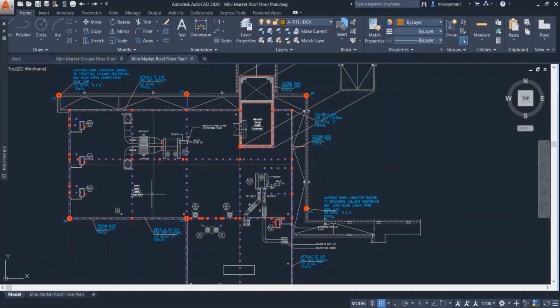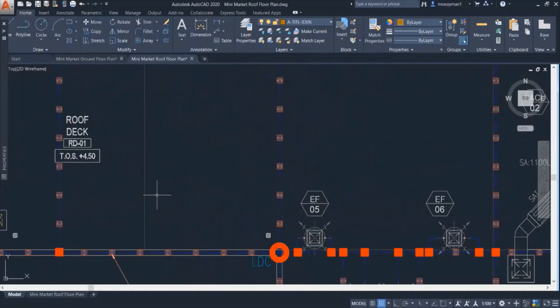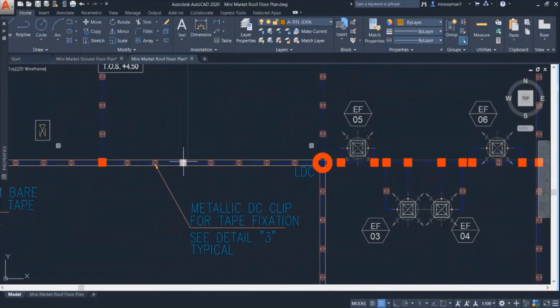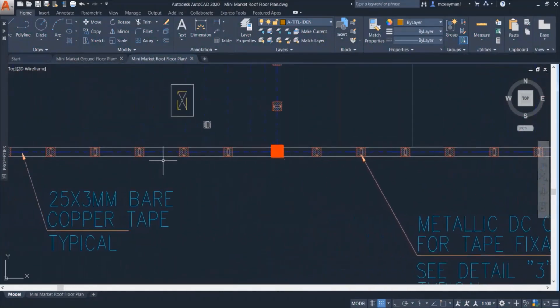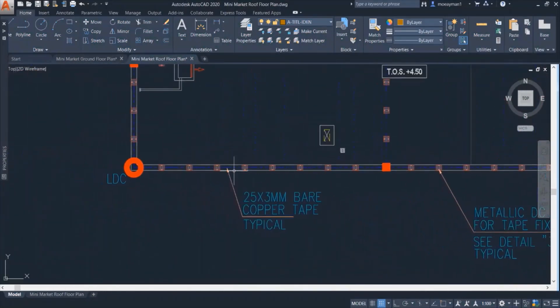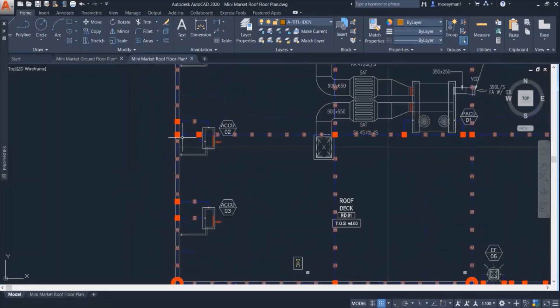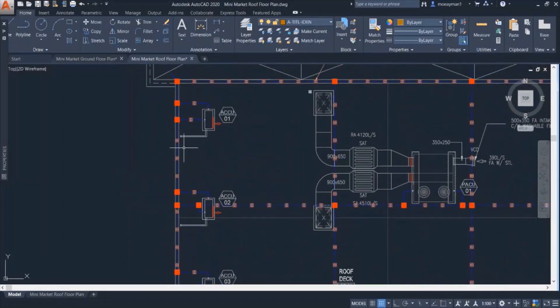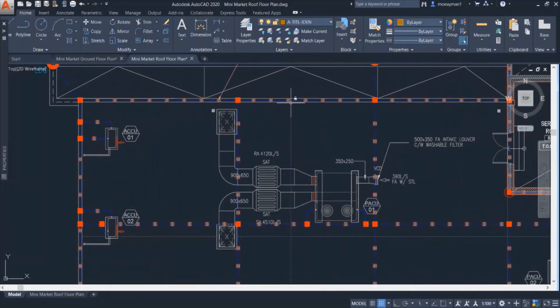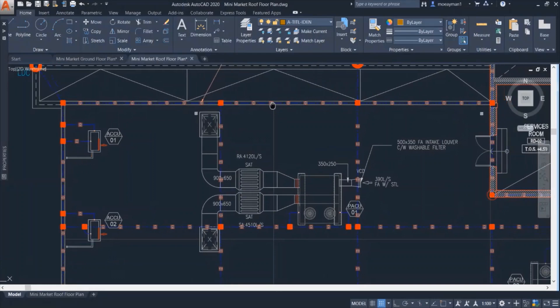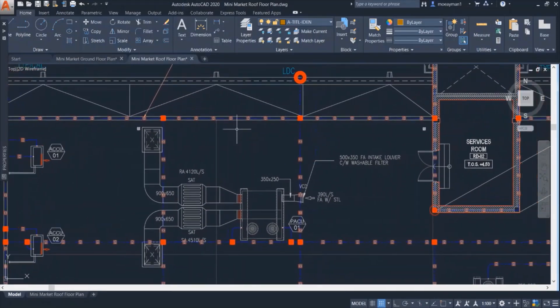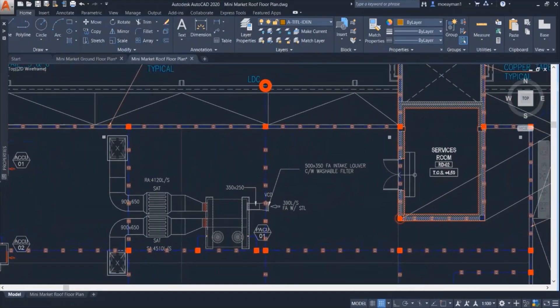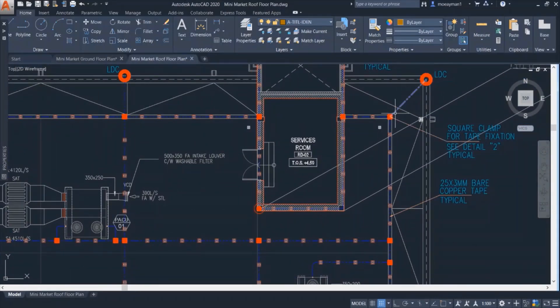We can also see that these mesh conductors are fixed on the parapet of the roof. So on top of the whole parapet of this roof we can see that there are copper tapes installed. Then from the parapet of this roof we can see that they are connected to a lightning down conductor.